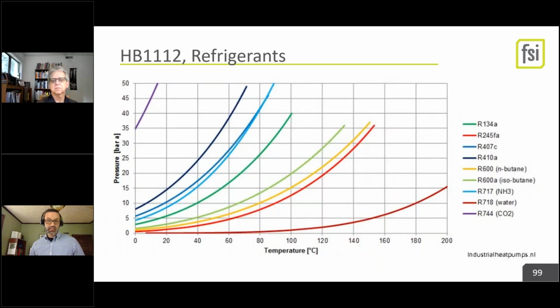Let's keep moving. So CO2, that's an obvious one, right? Like CO2, you've seen that as a refrigerant, and we do see that in heat pump water heaters. There's several manufacturers that already make them. And it only really works in packaged equipment because it's freaking high pressure. It's not just high pressure, it's this purple line off to the left here that's way above everything else. So freaking high pressure. So you need super thick coils to make it work and a really robust compressor. So running those coils out in split systems, we're not going to do that in CO2, except in rare cases. Like there's one CO2 water heater that'll do it. Next slide.